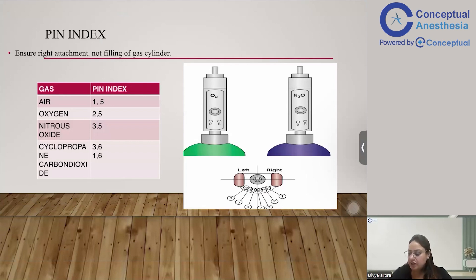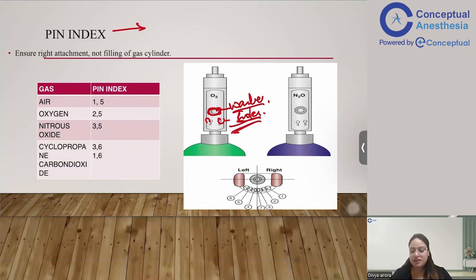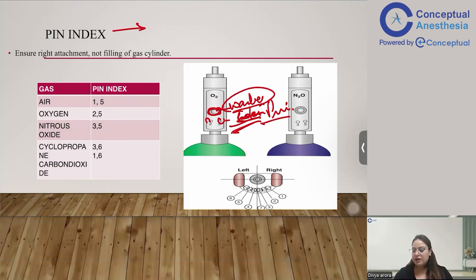Another safety feature is the pin index system. When you look at the cylinder, you'll see a washer and holes for pins. The pins are on the machine side; the holes are on the cylinder side. The pin index ensures correct attachment of the cylinder. However, its drawback — which examiners frequently ask — is that it ensures the right attachment but does not ensure the right filling of the gas inside.